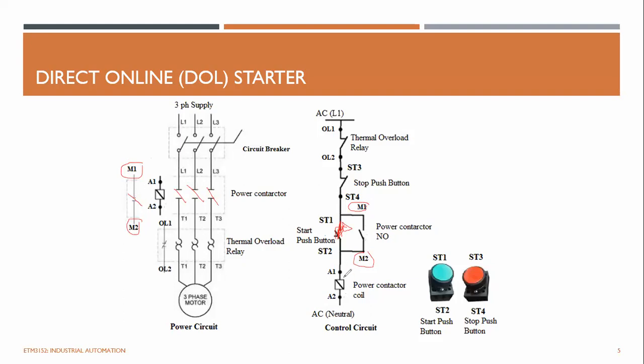As this is closed with this power contactor, this happens in a very short time. Someone presses this one, this closes, and this is also closing, right? Which means it's self-latching now, so the current can come forward from here. If this push button is released, the coil is still energized because it is self-latched now. This one is closed and this one is closed, and it keeps closing. So it's a latch. If someone wants to stop it, he can press this stop button here. So he can disconnect this, and the circuit is disconnected again.